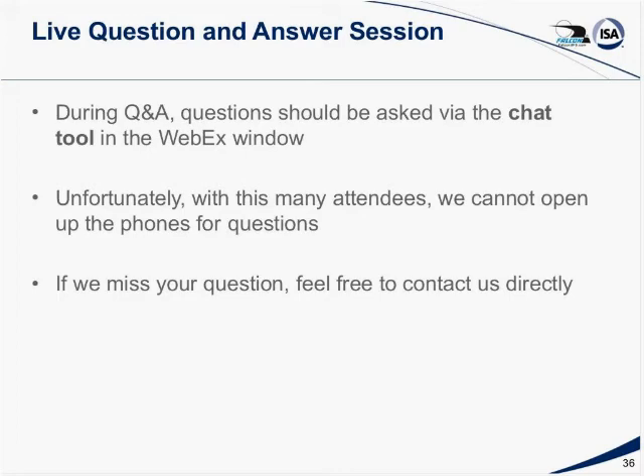Mike, we have a question that just came in about whether there is sizing help available to determine what size UPS you need. Yes, the best way to deal with sizing is to keep things in watts. A lot of UPS manufacturers rate the outputs for a load with a 0.7 power factor. Well, most people aren't going to know what the power factor of the load is. But if you take the worst case in watts, if your load is 10 amps at 120 volts, that's 1,200 watts. If you take that, you can't get in trouble.